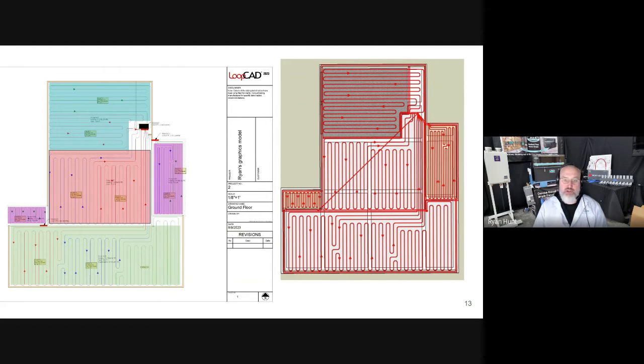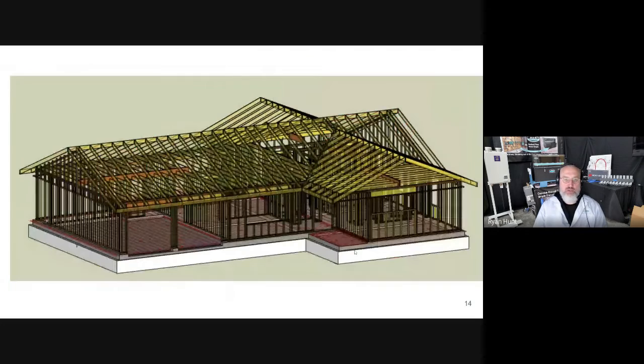So yeah, this is what it looks like here. I've incorporated some outdoor spaces, some patios. You see that they're denser. The tubing is laid 6-inch on center there and 12-inch on center in the rest of it because it's a slab on grade, one level with concrete. And this is what it would look like with the tubes in the floor.